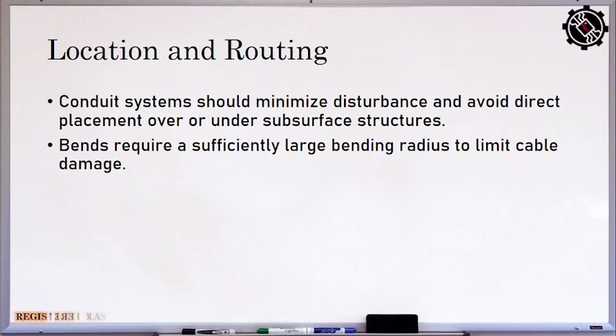Because our routing, our conduit system, passes there, it might become a reason for the building to collapse. Then bends require a sufficiently large bending radius to limit cable damage. The bending radius is usually 8 times the diameter of the wire, depending on the type of wire. You will find this in PEC Part 1, which we'll be discussing as we go on with our review. So it must be sufficient; we cannot shortcut the bending radius when it comes to underground supply lines.